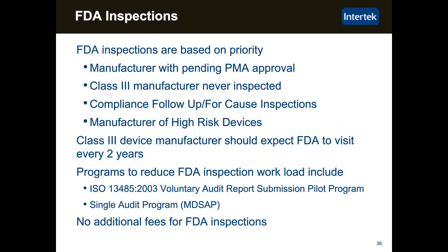You will be subject to FDA inspections. However, the FDA inspections are based on the following priority. A manufacturer that has a pending PMA approval is at the top of the list. A Class 3 device manufacturer that has never been inspected is right below the people that have a PMA in. Then a compliance follow-up or for-cause inspection is next in priority. And a manufacturer of high-risk devices is fourth in priority. Class 3 device manufacturers should expect the FDA to visit every 2 years.